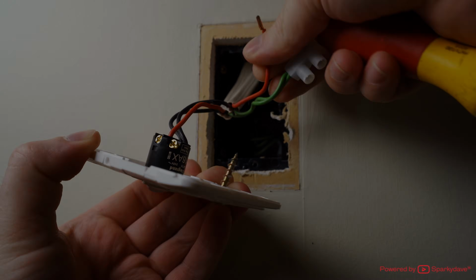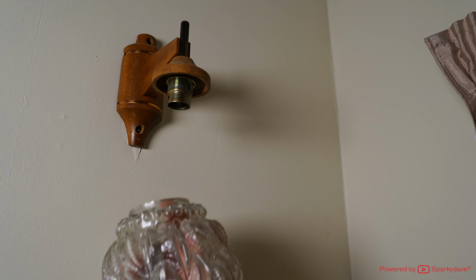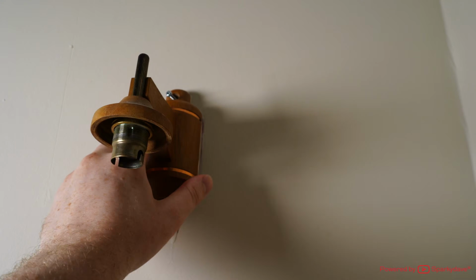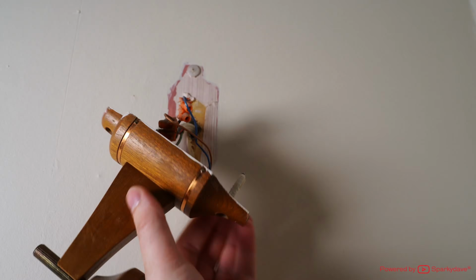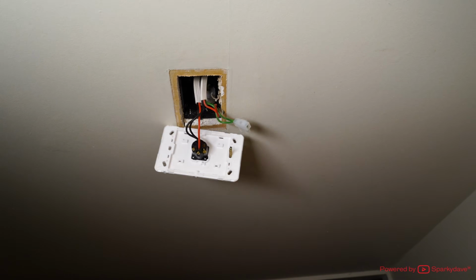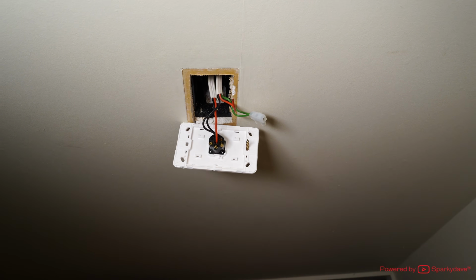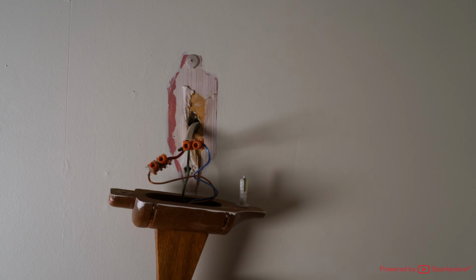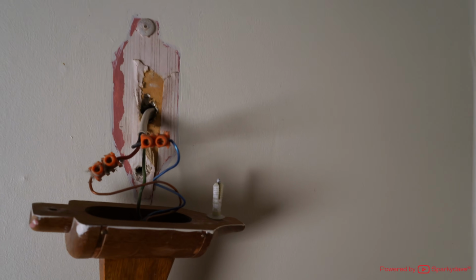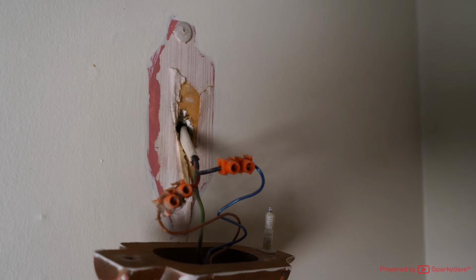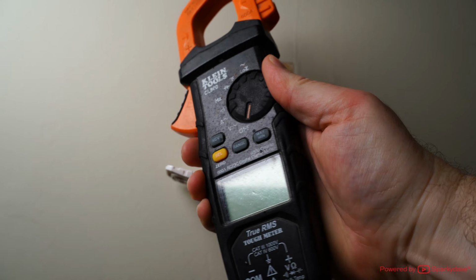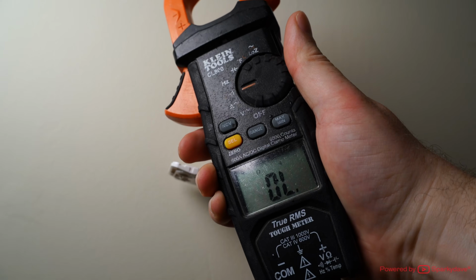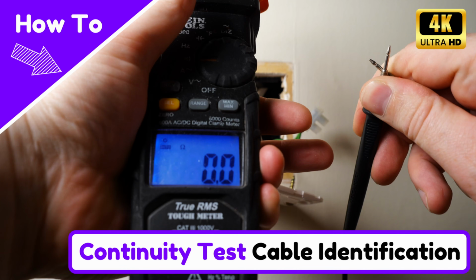Before disconnecting any cables behind the light switch, remove the light fitting from the wall and sight if the cable movement from behind the wall light is noticeable behind the light switch. In this instance, the cable is easily identifiable. If the cable is not easily identified, ensure the terminals at the wall light fitting are 0 volts and conduct a continuity test to identify the cable. I will upload a video soon demonstrating how to conduct a continuity test to identify cables.